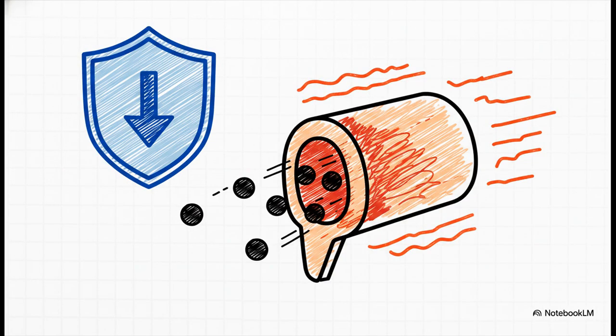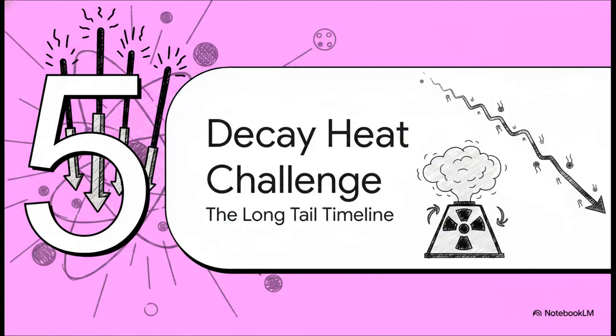But, okay, what if reactivity spikes unexpectedly? Well, the core actually protects itself within milliseconds through the Doppler effect, which is also known as fuel temperature feedback. Basically, as the uranium fuel heats up, the thermal motion of the nuclei causes the uranium-238 resonance absorption peaks to broaden. In plain English, the hot uranium essentially swallows up more neutrons, which immediately drops the reactivity. It's a totally inherent, universally negative feedback loop that safely limits power excursions without a human having to do a single thing.